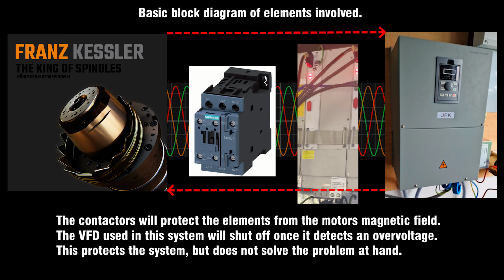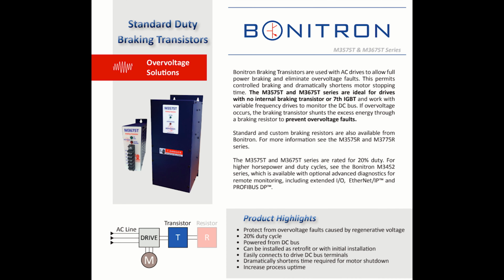So, what can be done about this? You can contact your drive manufacturer and ask for a DC bus clamping transistor or similar. It monitors the DC bus voltage, and when it exceeds the safe level, it will send excess energy into the braking resistor to be converted into heat, preventing the overvoltage before it even starts. If your manufacturer doesn't make such a product, which would be very unlikely, there are a few companies who make their own version which will work on any VFD that has its DC bus terminals accessible. A company based in the US called Bonitron makes some great looking products for this application, and it's most likely who I'm going to go to for my solution. They make an external braking transistor which will clamp the voltage at a set level and prevent overvoltage alarms, thus allowing any machine with regenerative current capabilities to run without fail.